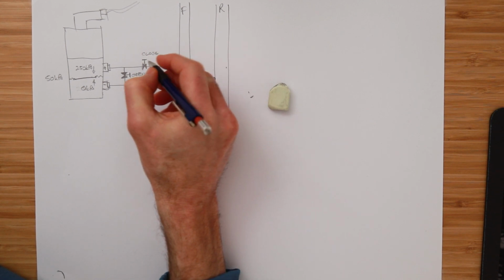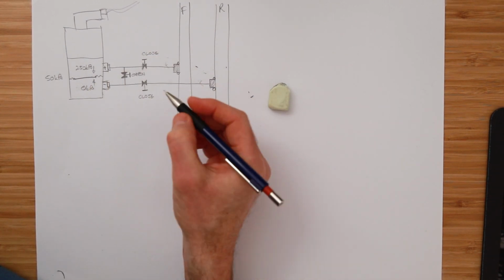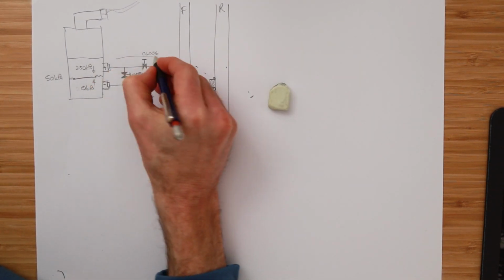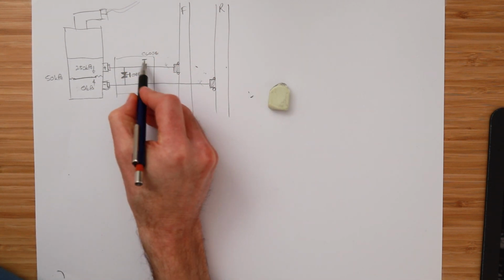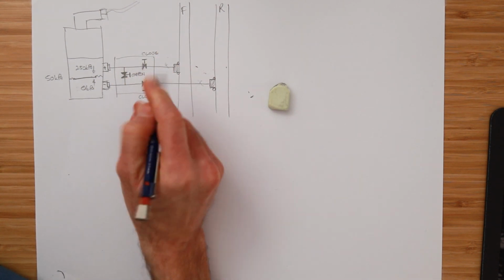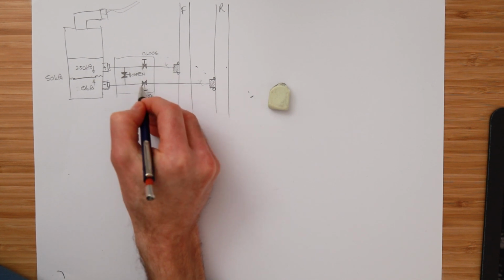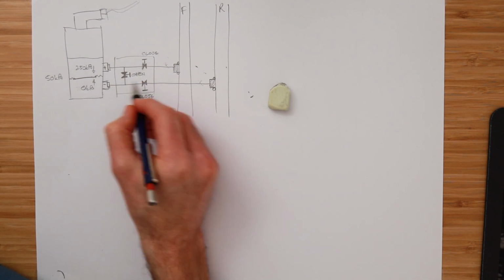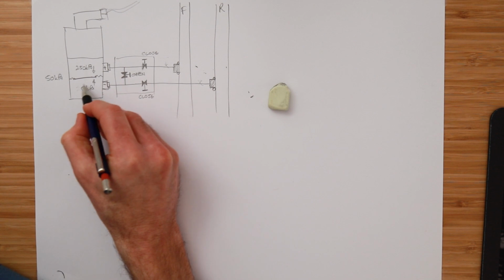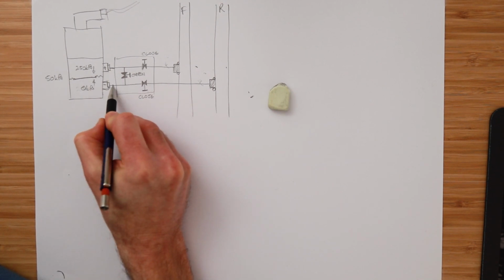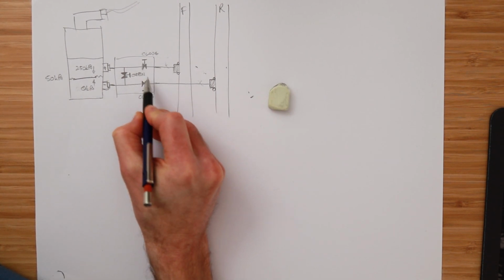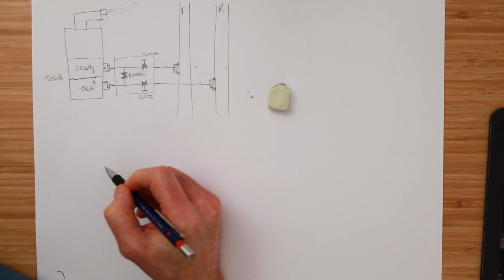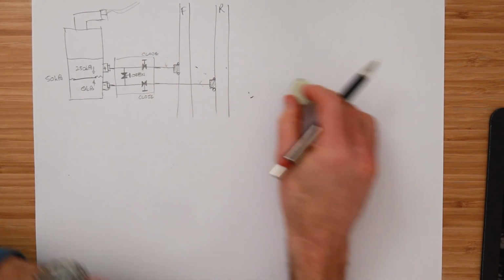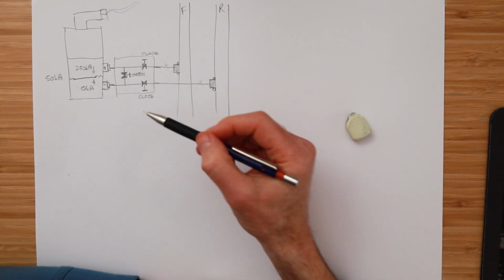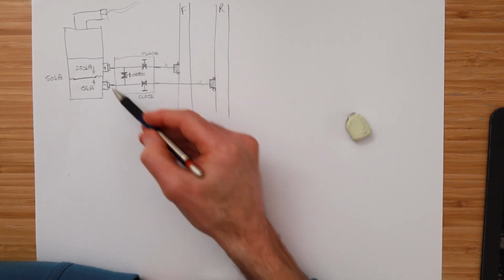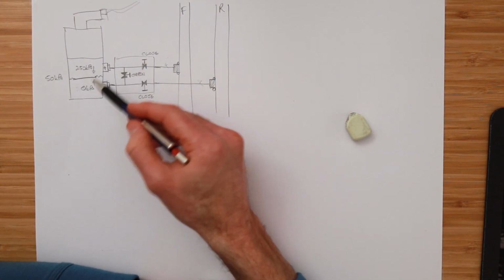But you can also get a little plate made up. And I call this a manifold. I don't know if it's the right name. But a little plate made up. So Mechanical makes a plate. They install these 3 tiny little manual valves in their factory, and then they install this thing next to the transmitter. He's got to make this pipework connection here and these 2 pipework connections here. I call this a manifold. I'm not sure if it's the right name to call it. So the first takeaway here is, if you're a BMS person, you need to be aware of this. Otherwise, you're going to have burst transmitters.